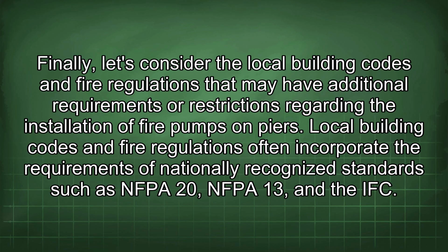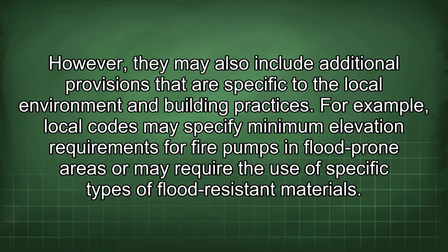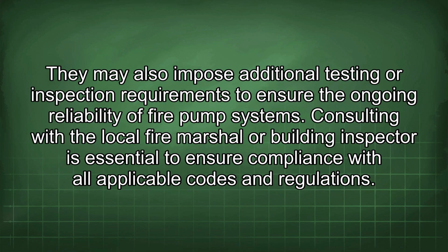Local building codes and fire regulations often incorporate the requirements of nationally recognized standards such as NFPA 20, NFPA 13, and the IFC. However, they may also include additional provisions that are specific to the local environment and building practices. For example, local codes may specify minimum elevation requirements for fire pumps in flood-prone areas or may require the use of specific types of flood-resistant materials. They may also impose additional testing or inspection requirements to ensure the ongoing reliability of fire pump systems.